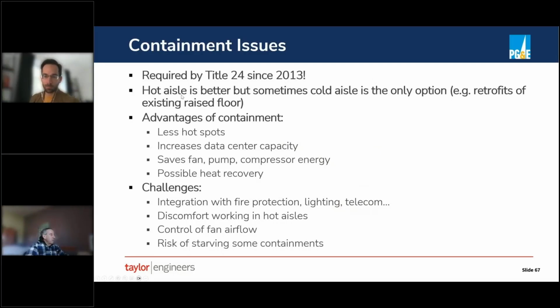Hot aisle in general is better because it keeps more of your space at a more reasonable temperature for human beings, but sometimes cold aisle is the only option. If you're retrofitting an existing raised floor data center, that's almost always the only option that's going to be available. Containment, again, reduces hotspots, increases capacity. We've had data centers that simply haven't been able to put in the servers because they've run out of air, if you will. Without containment, you need to blow a lot more air than your servers are pulling. And so they often run out of airflow capacity before they run out of electrical capacity.